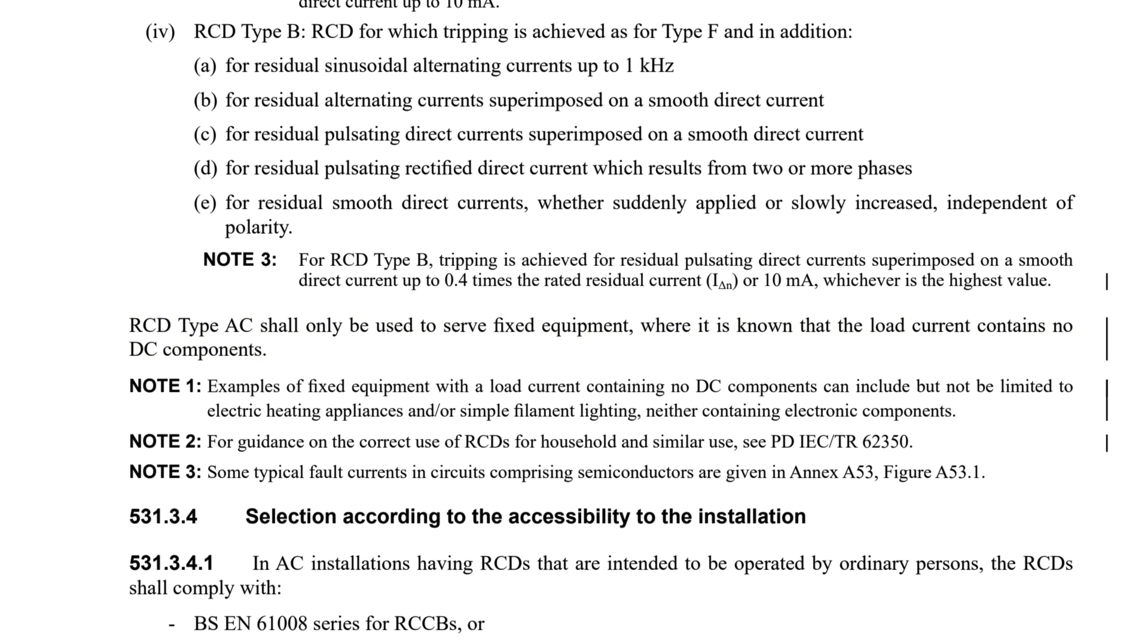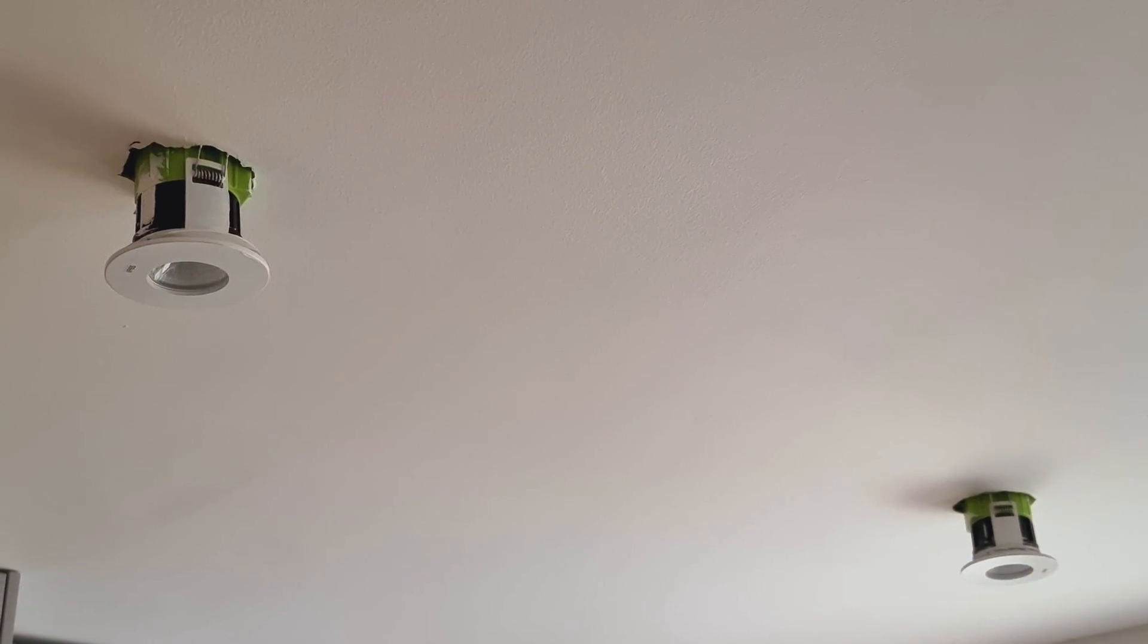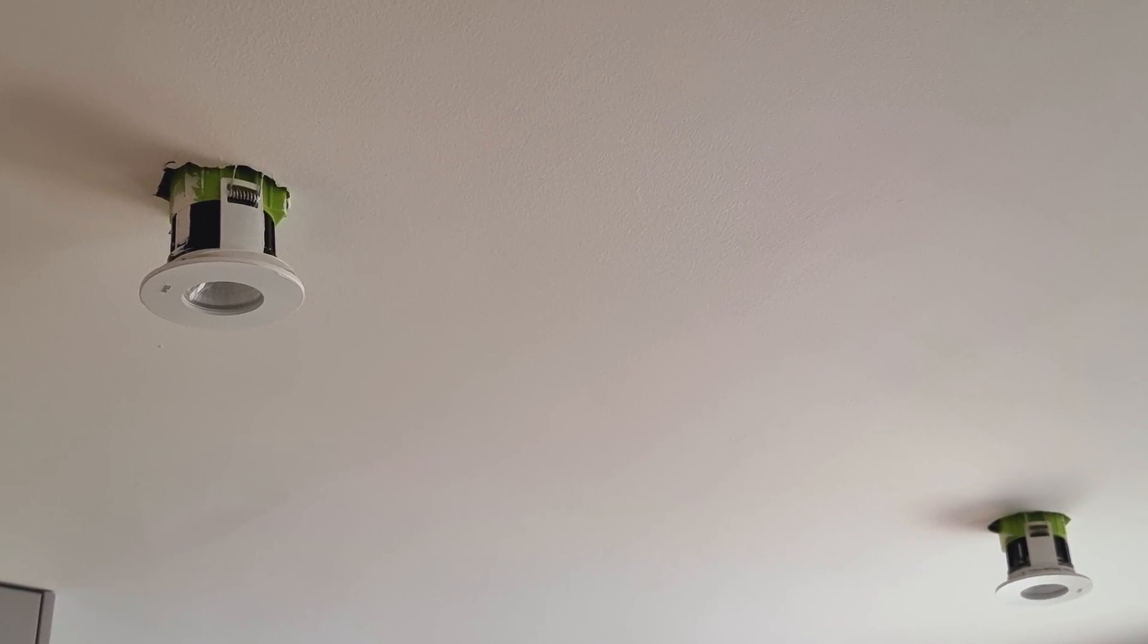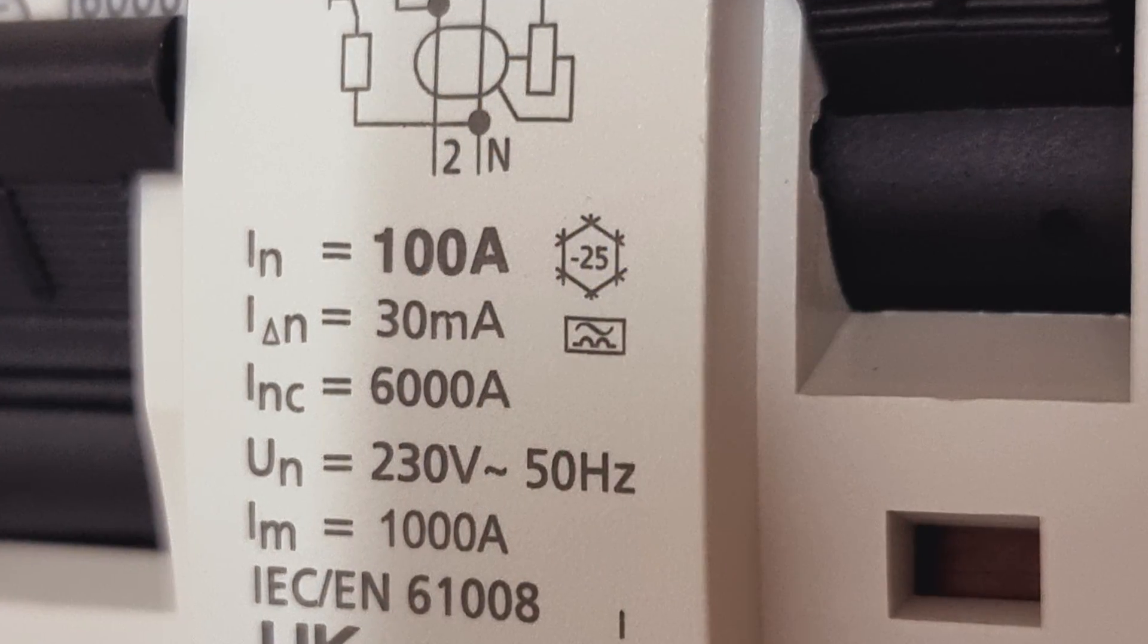Note 1 just below adds further insight as to just what an AC type RCD can be used on, where it says, examples of fixed equipment with a load current containing no DC components can include, but not be limited to, electric heating appliances and or simple filament lighting, neither containing electronic components. As you can imagine, in this day and age where the simplest heater may well incorporate digital controls or lighting will be based on LEDs, it seems that the type AC RCD may well be breathing its last, and the base level of RCD protection will be the type A moving forward.